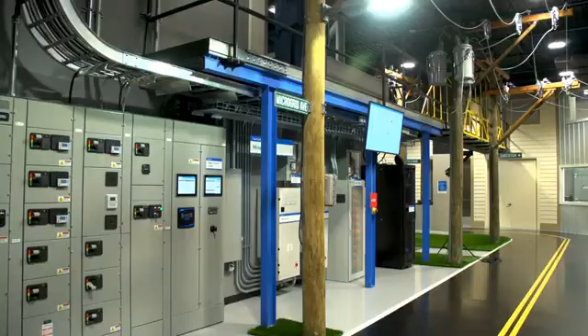In some cases, severe disturbances can result in complete loss of power. Some microgrids are capable of independently restoring voltage to the loads. This is called a black start. At the PSEC, our microgrid can utilize either energy storage batteries or the natural gas generator to restore power. This occurs automatically, and the source is selected based upon user-defined priorities.